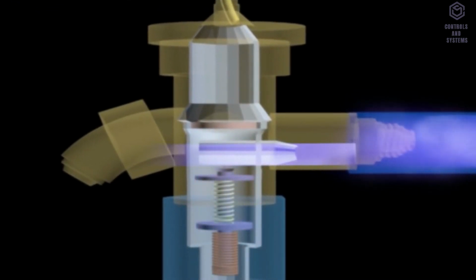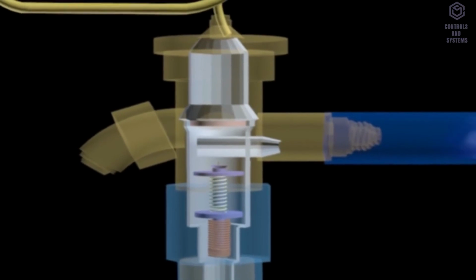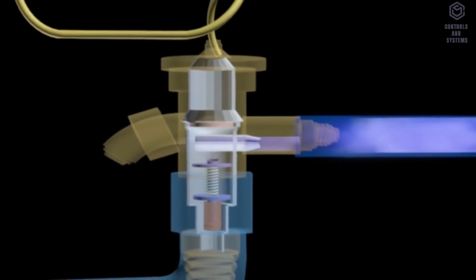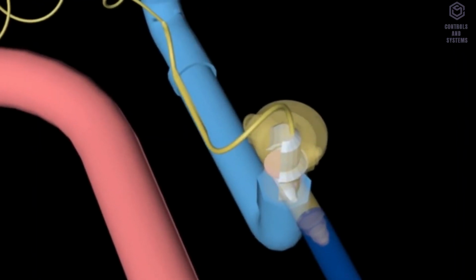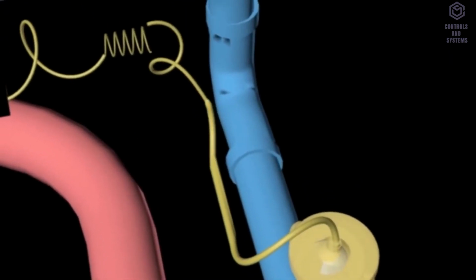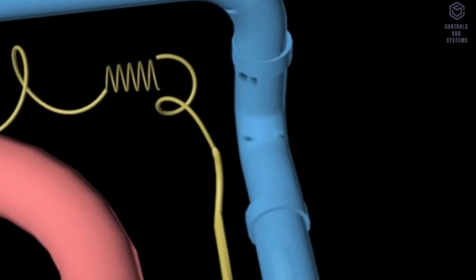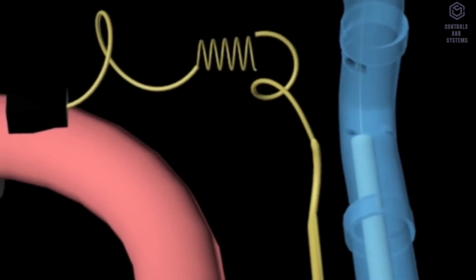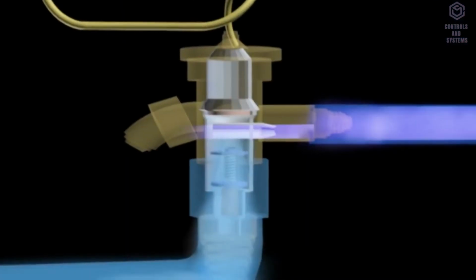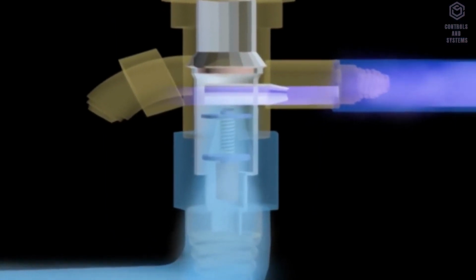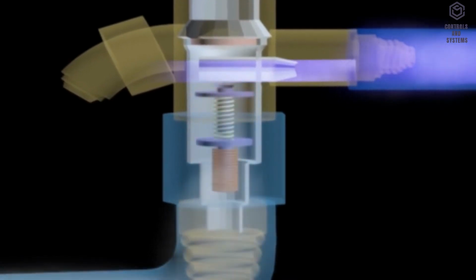It works according to the temperature of the refrigerant which comes out from the evaporator. The sensing bulb placed on the outlet of the evaporator detects the temperature of the refrigerant and sends the signal to the TXV. The needle valve in the TXV will control the flow of refrigerant based on the transmitted signal.